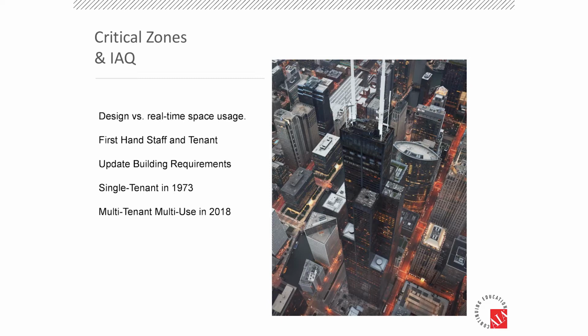This required that we walk the building to document conference rooms, large gathering areas, and dining spaces, and take multiple IAQ readings per floor over 4.5 million square feet of building. It took about 5 days of walking the building with one of their in-house engineers, hitting every floor.